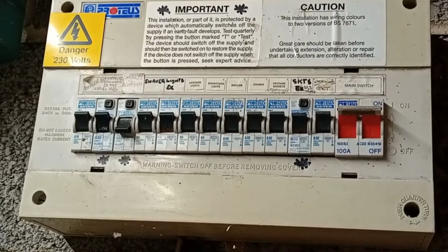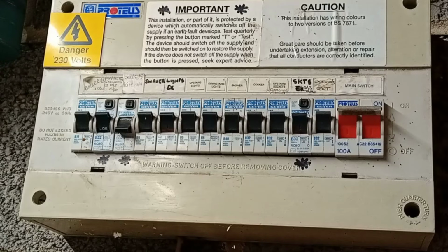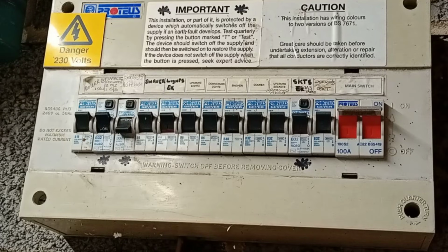Right, I'm back in the garage now. I've unplugged all the appliances. So we're going to try to turn the breaker back on and see if it stays on. If it stays on, what that'll prove is that one of the appliances that we've unplugged is at fault, causing our circuit breaker to trip. If it does reset and hold in, then what we can do to identify which appliance it is at fault is to plug them in one at a time, come look at the breaker and see if it trips it out. One of the appliances would trip the breaker out if it is an appliance at fault, and then we can easily identify the faulty appliance, okay?